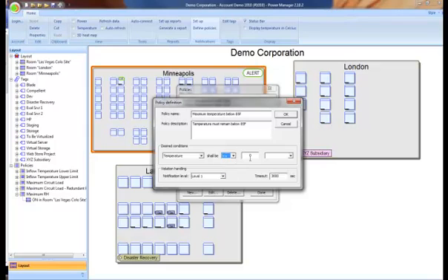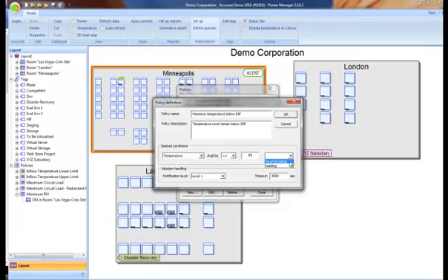In this case, we want it to be less than or equal to 85 degrees. And we choose the absolute reading option as opposed to the relative reading option. You would use the relative reading option in a situation like power readings where we know the rated capacity of the power cable and want to be notified if usage exceeds a certain percentage of that rated capacity.